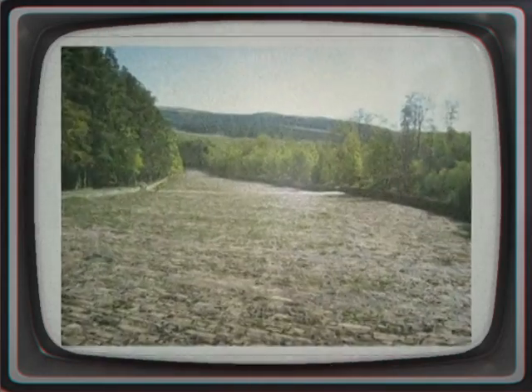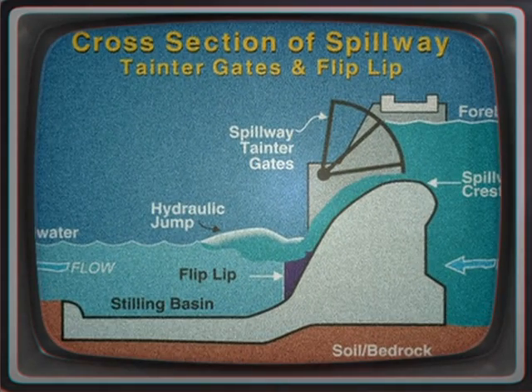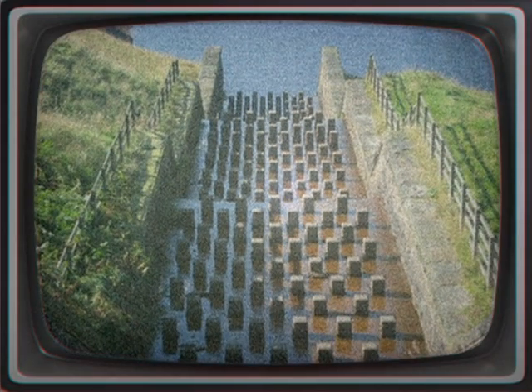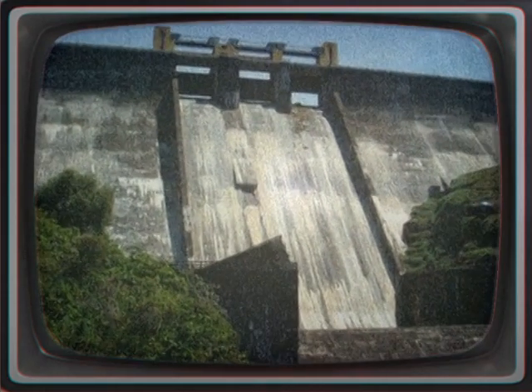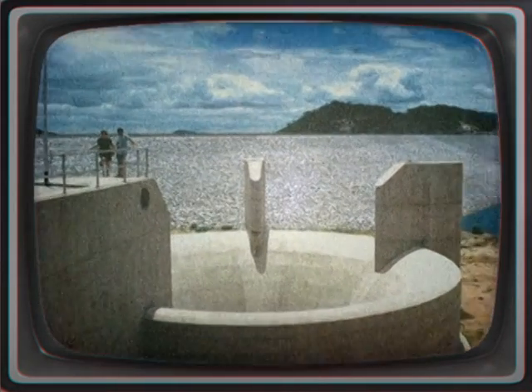In an intermediate type, normal level regulation of the reservoir is controlled by the mechanical gates. If inflow to the reservoir exceeds the gate's capacity, an artificial channel called either an auxiliary or emergency spillway that is blocked by a fuse plug dike will operate. The fuse plug is designed to overtop and wash out in case of a large flood, greater than the discharge capacity of the spillway gates.